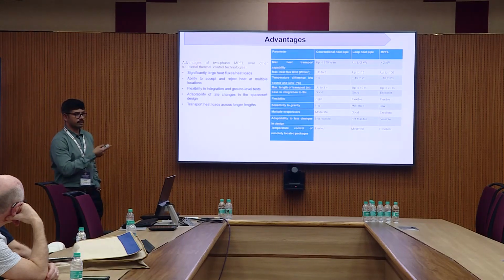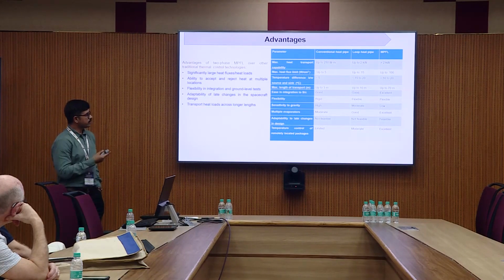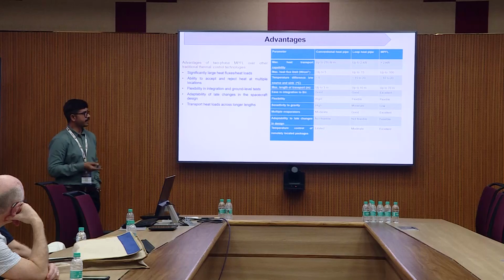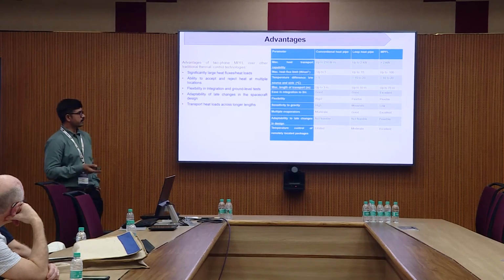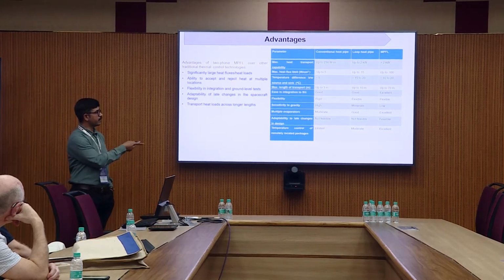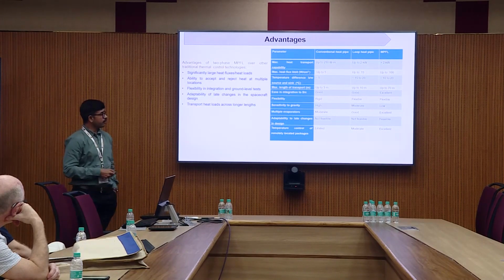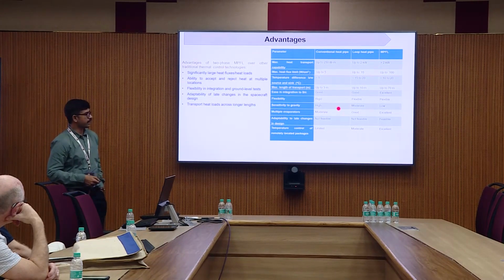However, the temperature difference delta T we can maintain, and the length of the transport, will be very high. Ease of integration is excellent. Flexibility is good. Sensitivity to gravity is very low, because the rest of the heat pipes and loop heat pipes have a high sensitivity towards gravity.